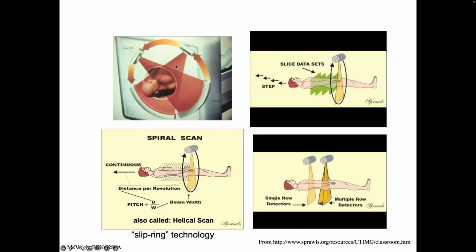Siemens did an interesting thing, and they built a scanner that has 2 X-ray tubes and 2 detectors, and they're pretty well 90 degrees apart. So essentially, you're getting a much higher angle view simultaneously, and so you're scanning twice as fast in that case. And so they went down that direction, as opposed to making their detector in Z very large.